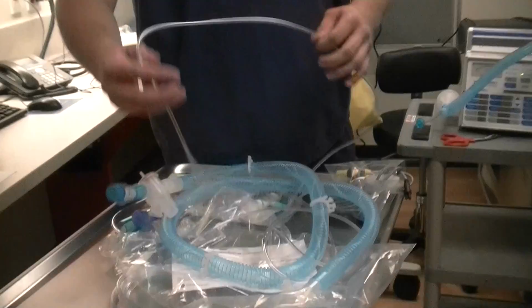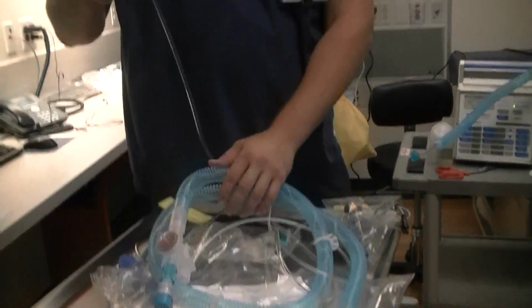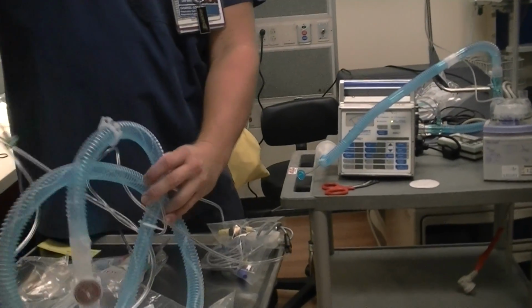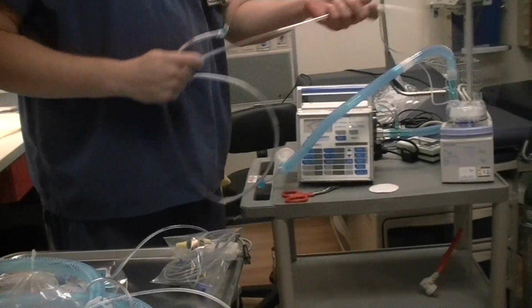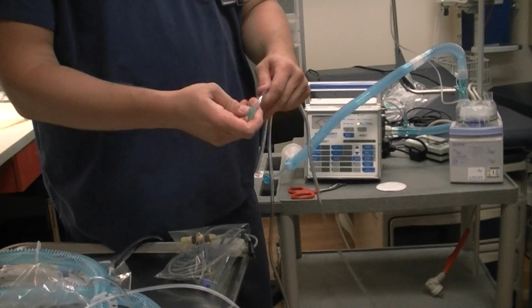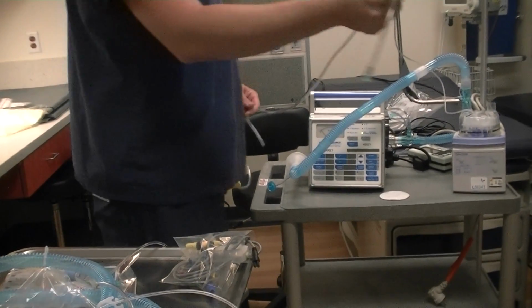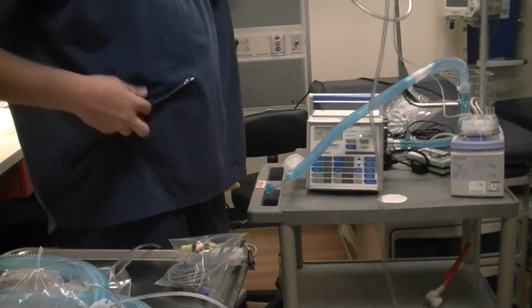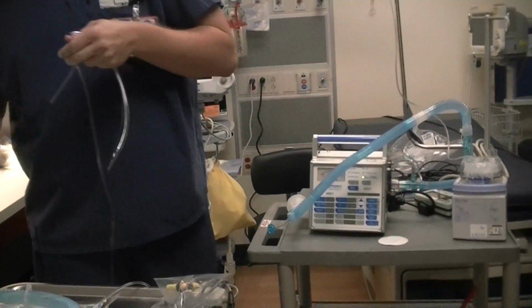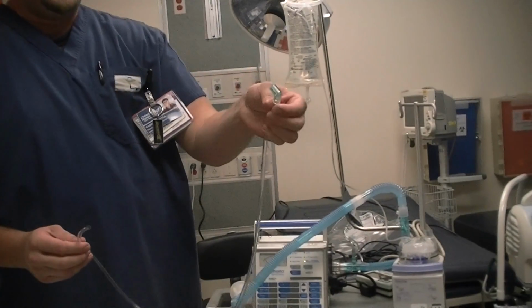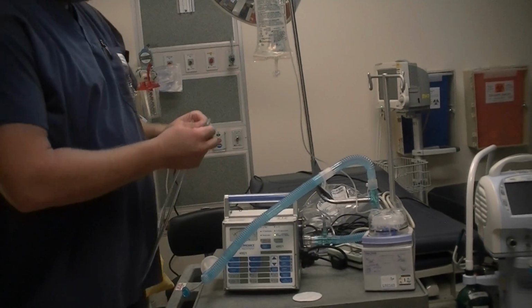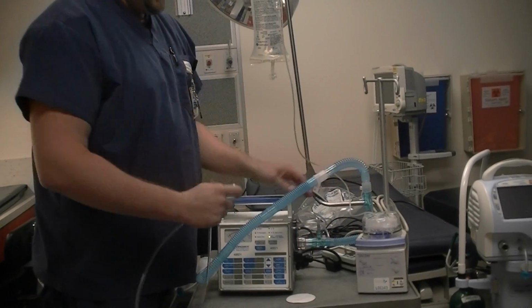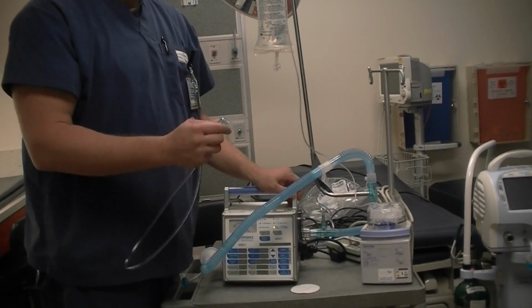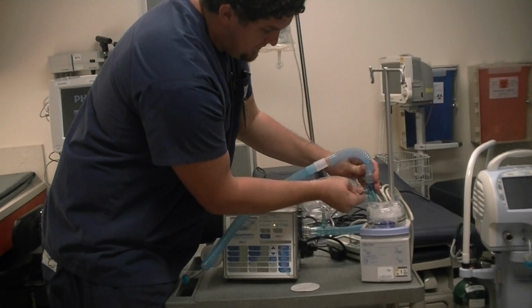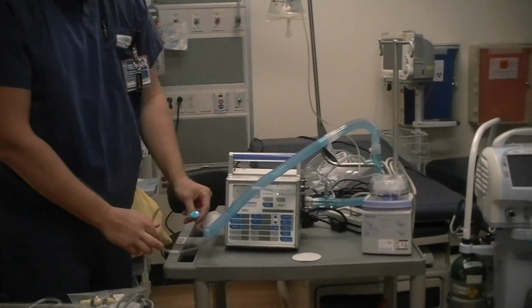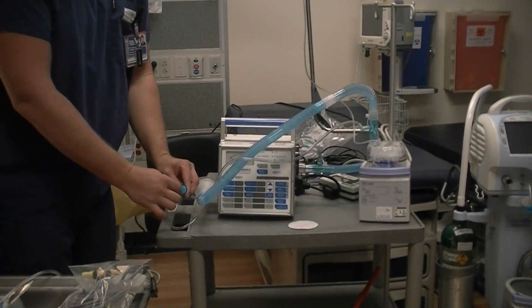Okay? Next, we're going to grab our pressure line. This is the pressure line that is connected to the ventilator. You want to grab the line that has the green adapter piece on it. What you want to do with this is give it a quick measurement. You're just going to cut this. Grab your piece that has the green adapter on it and make sure it's long enough. You want to put this adapter line as far away as you can from the ventilator, but keep it on the dry side. So we'll hook it up to our pressure line adapter here, and this will connect to your blue proxy line adapter down here.